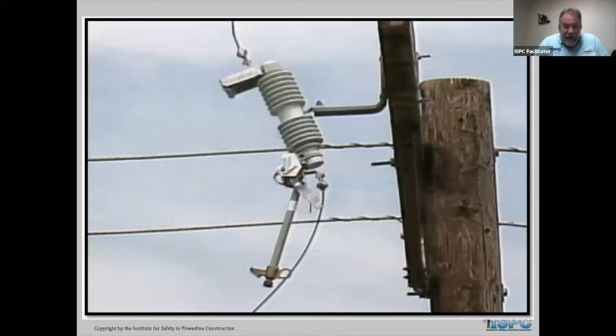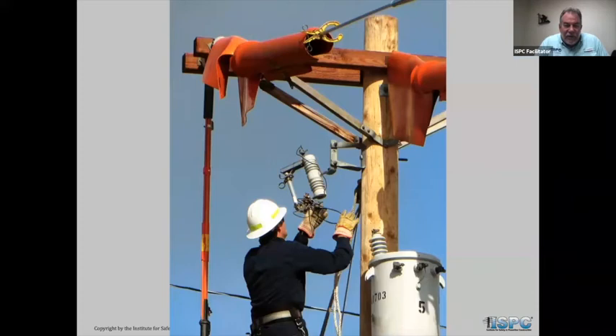So what you just saw was a 15 kV rated cutout barrel, cutout assembly. And here is a 25 or 35 kV. So you can just see how the whole body itself is a little bit larger. The fuse is a little bit longer. So the higher the voltage, the more insulation we actually need. Here's just a typical guy putting in a cutout on top of a transformer from off the pole.